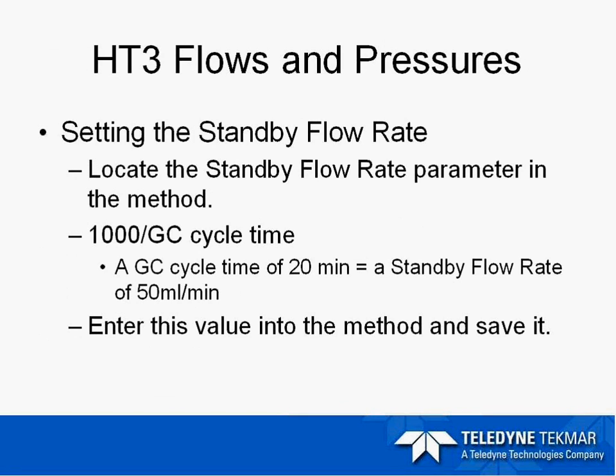Now moving on to the HT3, which is our replacement for the 7000. The HT3 comes as a static loop-only system or a dynamic option which comes with a trap. While the static unit is very similar to the 7000, the technology is slightly different in how it measures gas flows and pressures. The HT3 has a mass flow controller instead of a pressure regulator and gauges like on the 7000, giving much better control of flow and pressure. The incoming gas pressure to the HT3 must be a minimum of 65 PSI for the mass flow controller to function correctly, and it should not exceed 100 PSI.